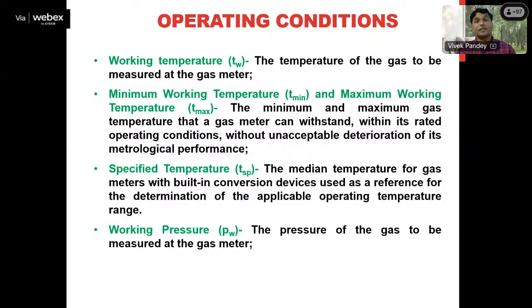And yes, there is a specified temperature range for all gas meters by the manufacturer, within which it will act accurately, like T minimum to T maximum. Suppose for a particular gas meter the specified temperature range is -10 degrees Celsius to 40 degrees Celsius. It means the manufacturer is giving the assurance that if it is operated within -10 degrees Celsius to 40 degrees Celsius, its accuracy will remain intact.